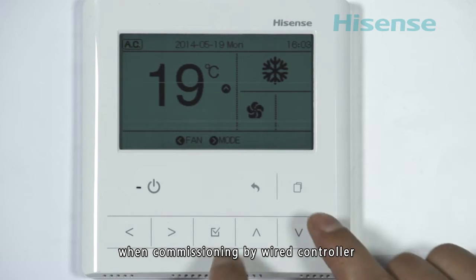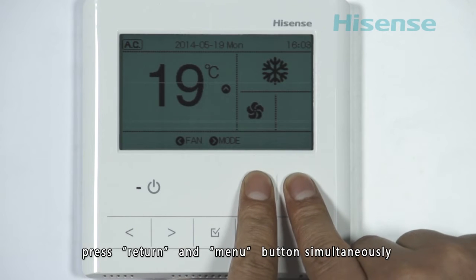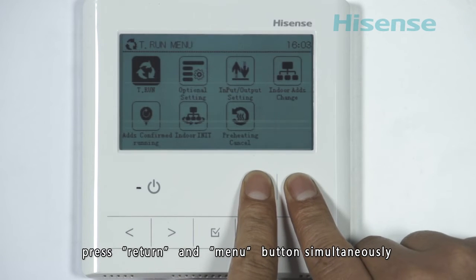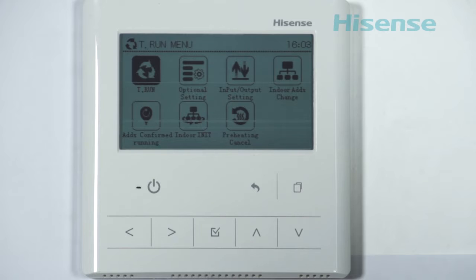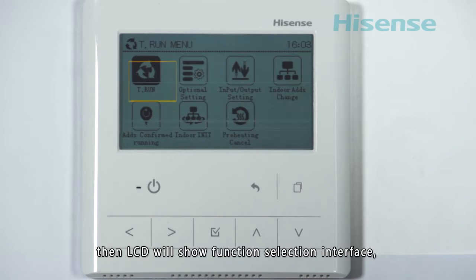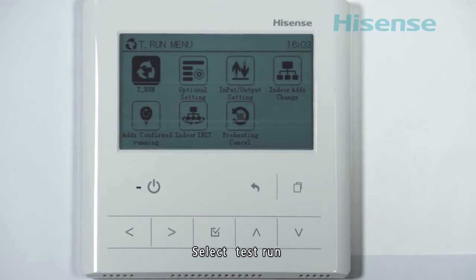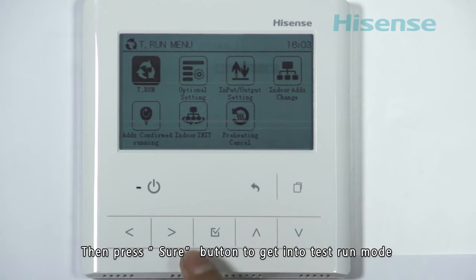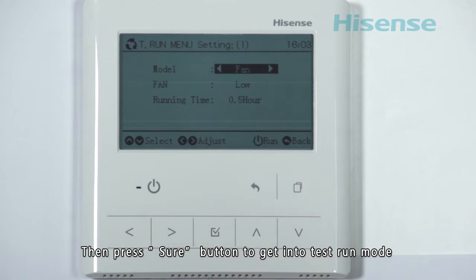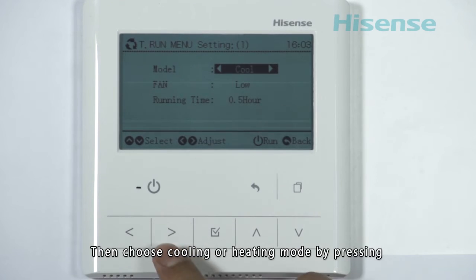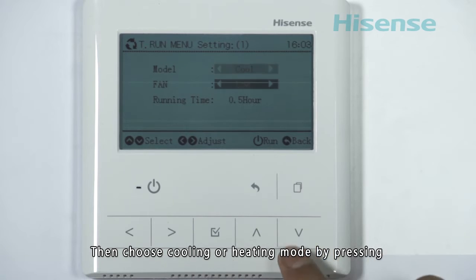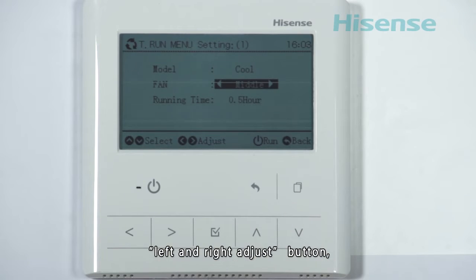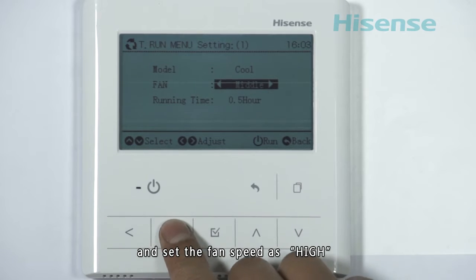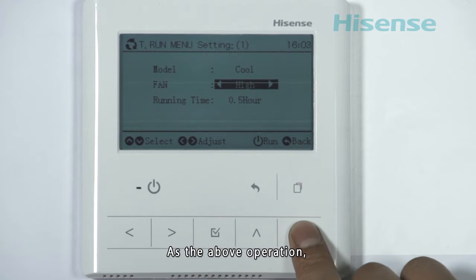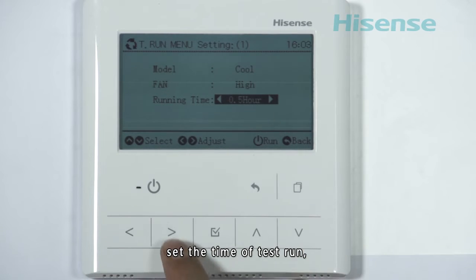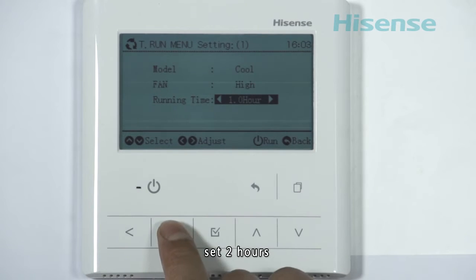When commissioned by wired control, press the Return and Menu buttons simultaneously for more than 3 seconds. Then the LCD will show the function selection interface. Select Test Run, then press the Sure button to get into test run mode. Then choose cooling or heating mode by pressing the left and right adjust buttons, and set the fan speed as high. As in the above operation, set the time of the test run to 2 hours.